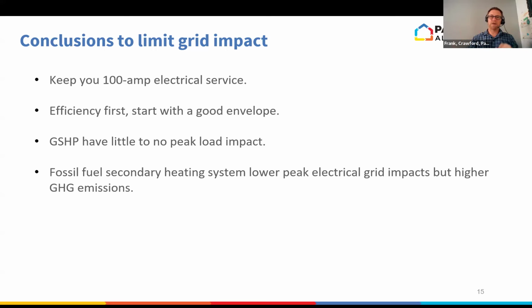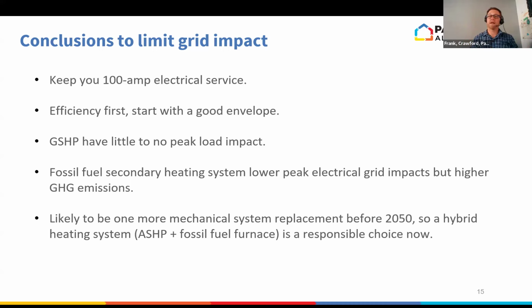So deciding our secondary fuel source is still definitely up for debate. If we're trying to meet the goal of net zero energy, no greenhouse gas emissions, or no longer using natural gas at all by 2050, we'll likely still have one mechanical system replacement before then, because furnaces, as they become more complex, probably won't last much more than 20 or 30 years. So if you want to do an upgrade now, put in that hybrid system with an air source heat pump and a fossil fuel furnace - that's probably fine. Then design it so that as you do your envelope upgrade, you use less and less gas, and eventually you can turn off the gas. The air source heat pump will then provide all the heating and cooling you need, while the blower fan from the furnace still moves air around your house.